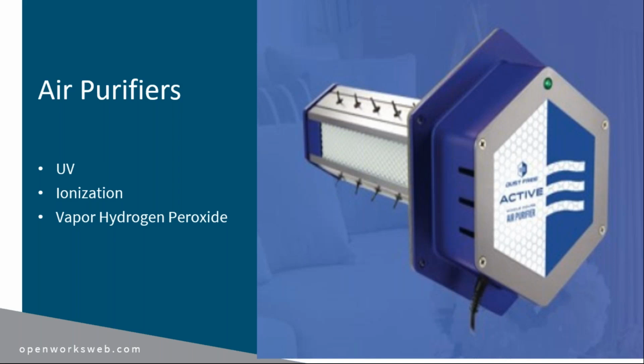In addition to neutralizing viruses, the technology will also attract to other particles in the air, and it turns microparticles into slightly larger specks of dust. Now the particles that were small enough to pass through the air filters are now becoming larger and being able to be caught by that air filter. This effectively increases the air filter MERV rating, and it can take additional stuff out of the air that it couldn't have before. What can be considered a downside of this technology, though, is particles that are suspended in the air may not make it back to the air filter. As they become larger and heavier, they can fall out of the air and land on your surfaces. This will make a room dustier and appear to be more dirty than it is.